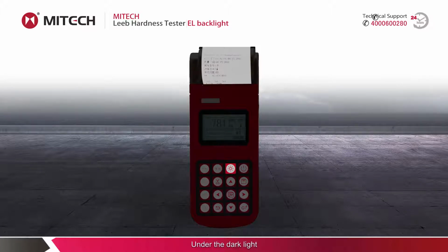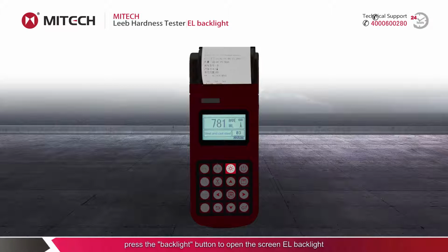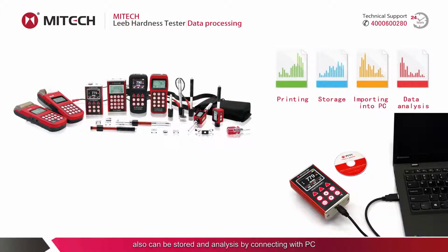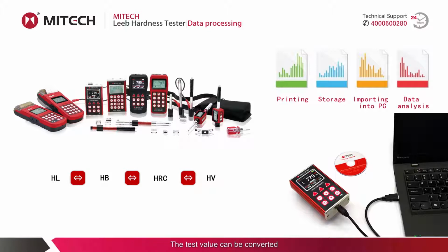In dark light, press the backlight button to open the screen EL backlight. When the backlight is turned on, the power consumption of the instrument will increase, so to save electricity, please turn off the backlight if not necessary. After the measurement, the value can be printed and preserved on the spot. It can also be stored and analyzed by connecting with a PC. The test value can be converted to a variety of hardness scales according to demand.